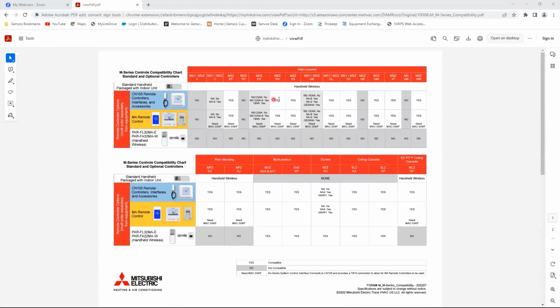Back up at the top, say we have a GE indoor unit. If that GE is an 06 through an 18 NA, the CN105 controller will not work with that unit. But if it's an NA-8 or NA-9, yes, it will work. I came across one of these, an 18 NA, and even though it had a CN105 port connector on the control board, it still does not work—they didn't activate it. So compare your unit to the device you want to hook to it and make sure it will work before you install it.